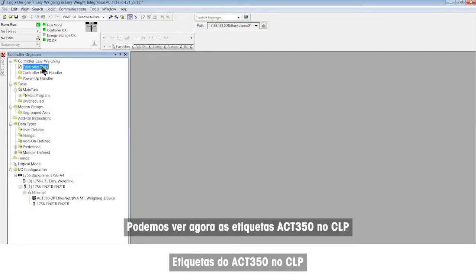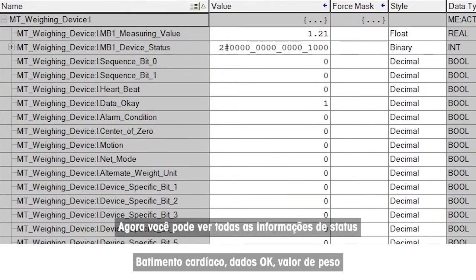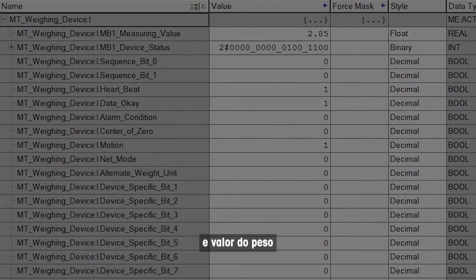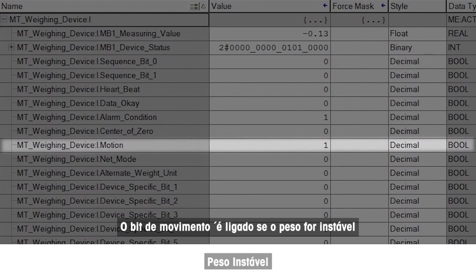We can now see the ACT350 tags in the PLC, including all status information: a heartbeat that shows connection, a data OK bit, and weight value. The alarm bit is on if any error such as under load is detected. The motion bit is on if the weight is unstable.